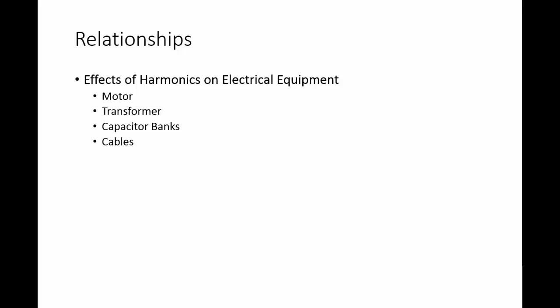The flow of current in a cable produces power losses and current distortion. The effective resistance of the cable is proportional to frequency due to skin effect. It is important to make sure a cable is rated for proper current flow, because both fundamental and harmonic current can flow in the conductor simultaneously.